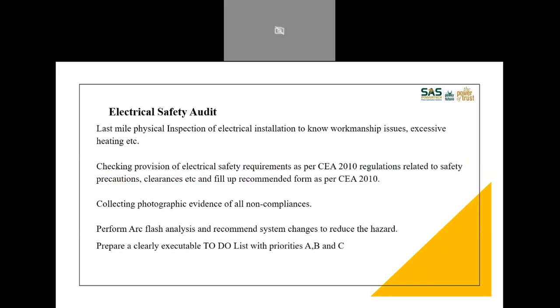Last mile physical inspection of electrical installations, to know workmanship issues and excessive heating, also needs to be included in that. Checking provisions of electrical safety requirements as per CEA 2010 regulations. See, if you go through these regulations, they have specified so many things. Clearance from wall to panel, clearance from door, all that is specified there. So whenever such an audit is done, a layout should be made, and whenever possible, the modifications also should be done. All of that makes sense. CEA 2010 is lengthy, but it is written very cleverly. All precautions are there.